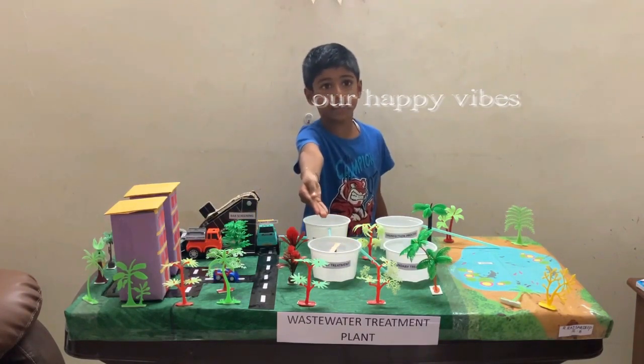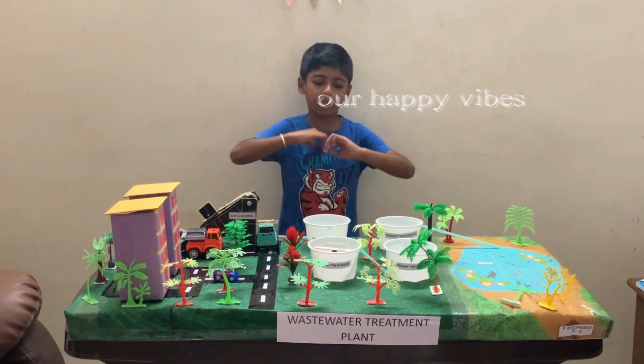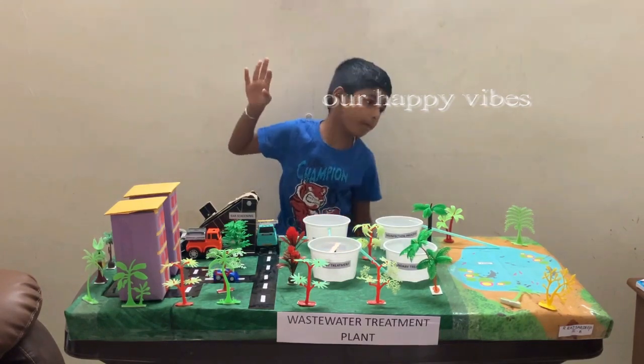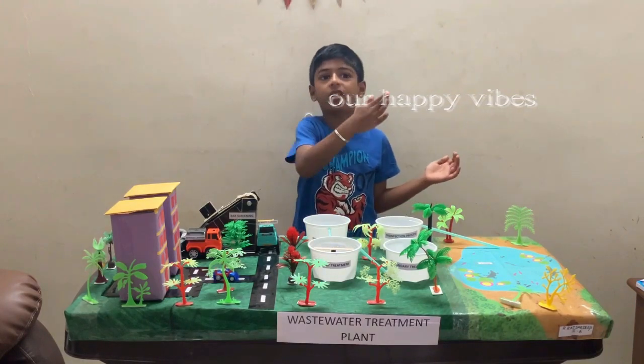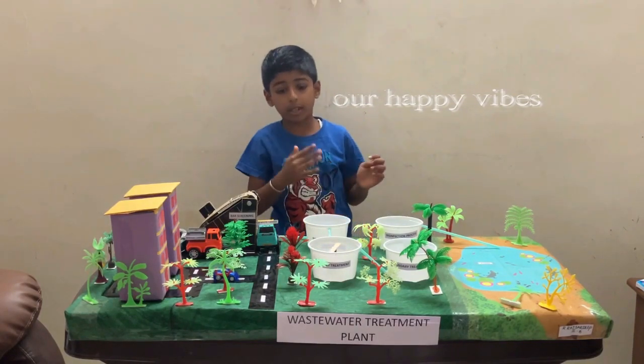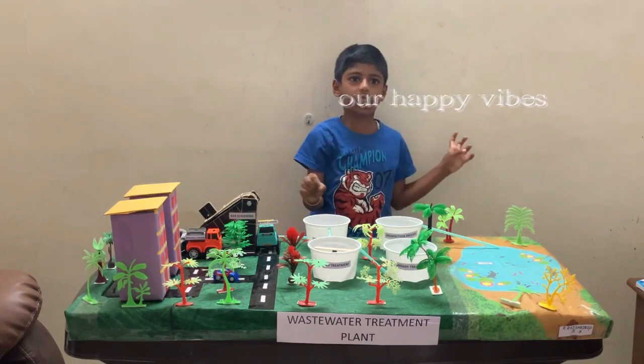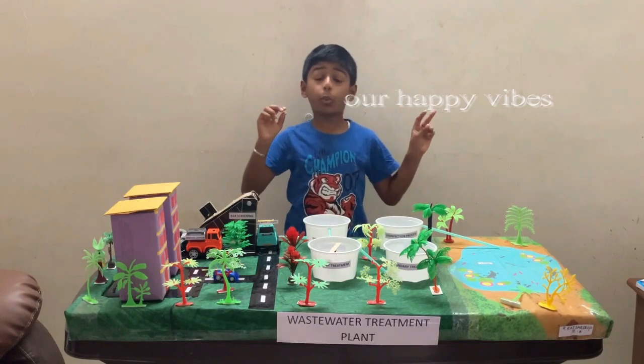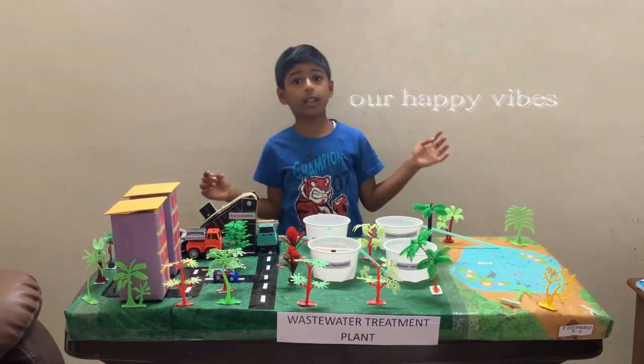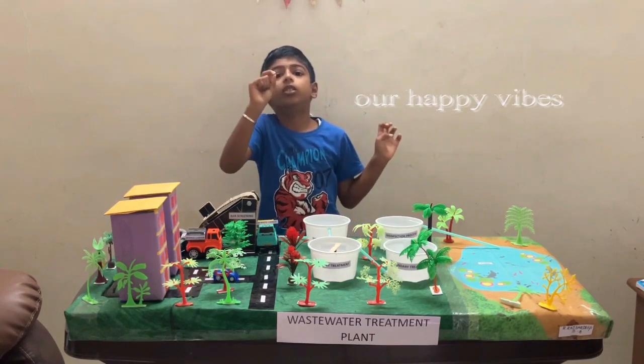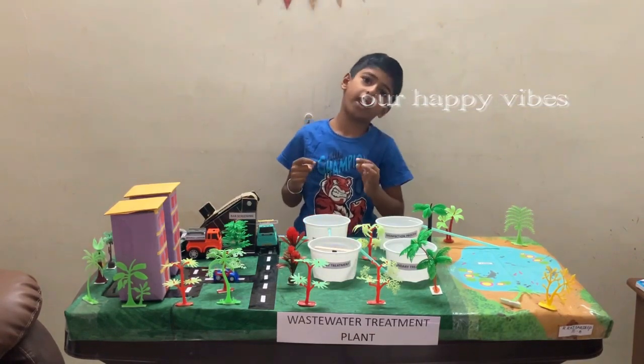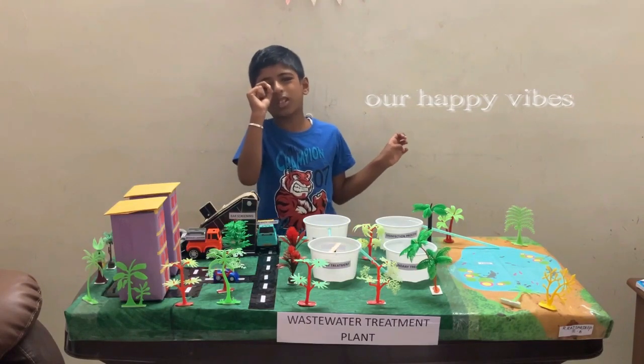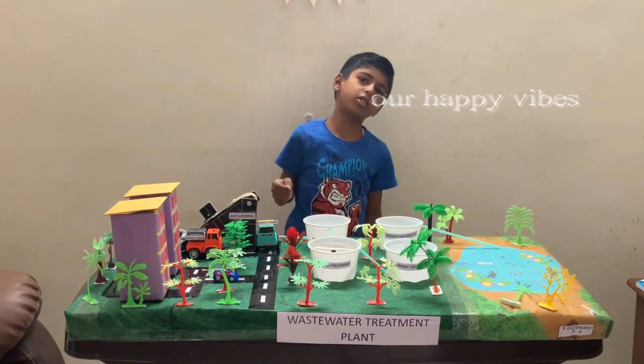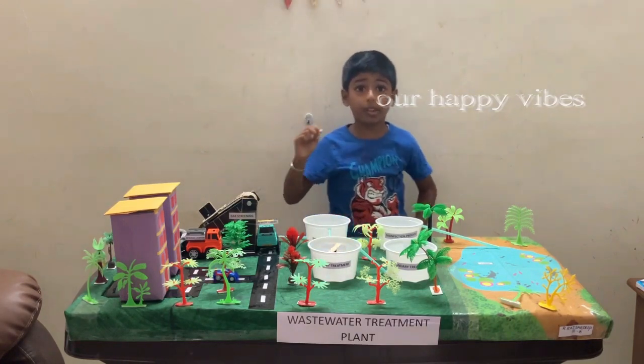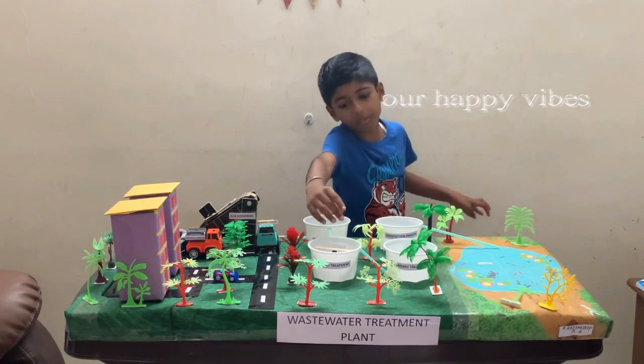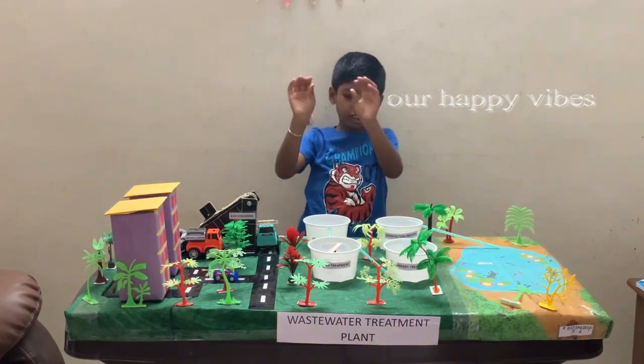Next comes primary treatment. Primary treatment begins with a large basin called the primary clarifier. This works on the principle of settling velocity, that means the speed at which a particle can settle. It's important to maintain the flow rate of the inlet water so that it doesn't exceed the settling velocity of the particles trying to be removed. Any particles larger than 10 micrometers are captured in this chamber. The top layer of the clarifier overflows into the next chamber of the process.